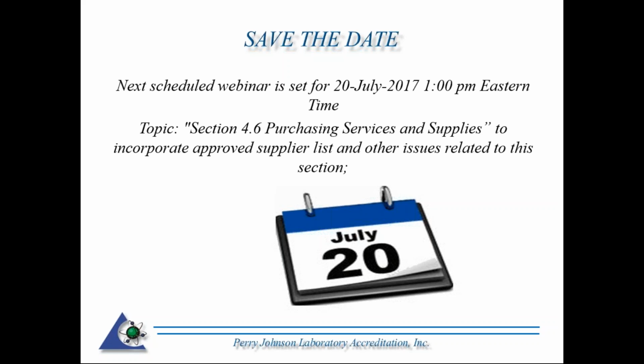And you have to bear with me. I realize you're a testing lab. I am the calibration program manager, so I tend to think a little bit more in those terms. Say you're requested to do work at the 2 kg level for a class 1 type of weight. You cannot subcontract under your scope of accreditation. I hope I'm making the correlation here between this and a gas lab, your question there. So not to say you can't subcontract it. You can subcontract it, but you just cannot do it under your scope of accreditation.